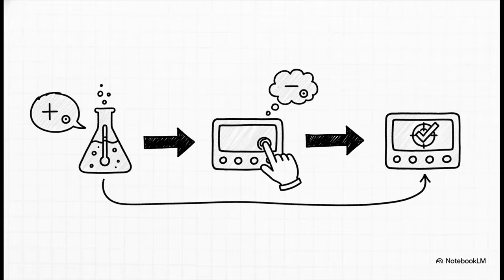So you might be asking, what's the point? Well, here's the magic. Once a calibration lab gives you a report that says, hey, at 500 degrees, this specific sensor reads 1.2 degrees high, you can't change the sensor, but you can go into your digital meter and program in a negative 1.2 degree offset. By telling your instrument to subtract that known error, you effectively cancel it out. And just like that, you are measuring the true temperature. And this is why, for the highest level of accuracy, you always calibrate the sensor and the meter together as a complete system.